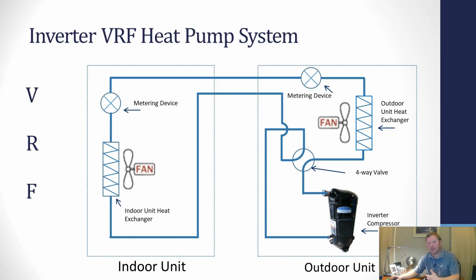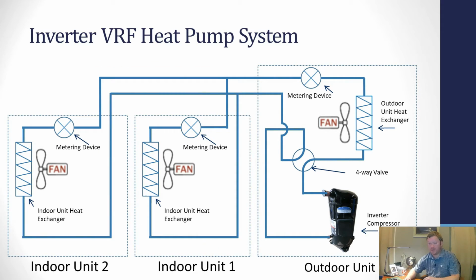The mini splits can't control superheat and subcooling directly like a VRF system can. Everything has to be done by the inverter compressor when you're looking at a mini split. Everything is controlled off of the discharge pipe temperature. When you go to the VRF system, now I immediately have more components that allow me to directly control the heat transfer at each indoor unit, which by doing this controls the room temperature of each indoor unit much more accurately.